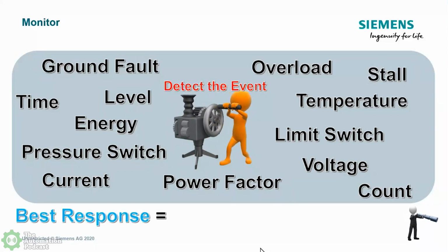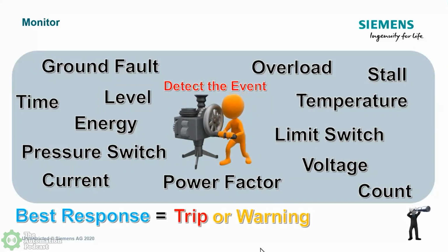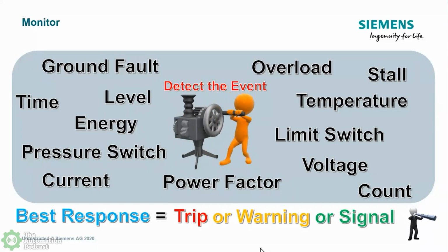But as I stated, I have the ability to give the best response of how you want to act and react to it. You could trip on them, you can warn, or we could do a signal. Now the differences are, signal means that I'm going to do some type of bit toggle, that I'm going to change it and have it go high from 0 to 1 and show up at the operator's panel just to let them know that, hey, this has happened.